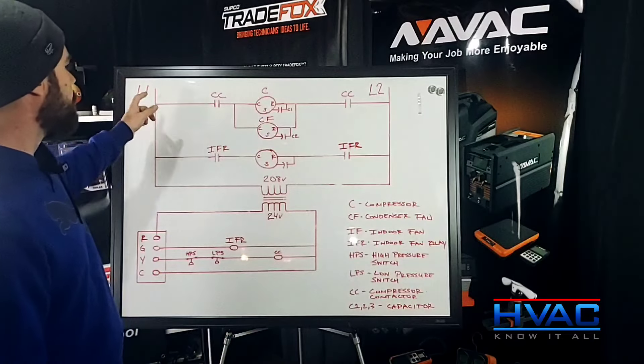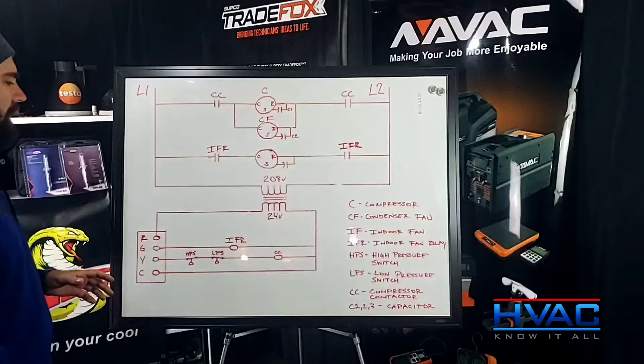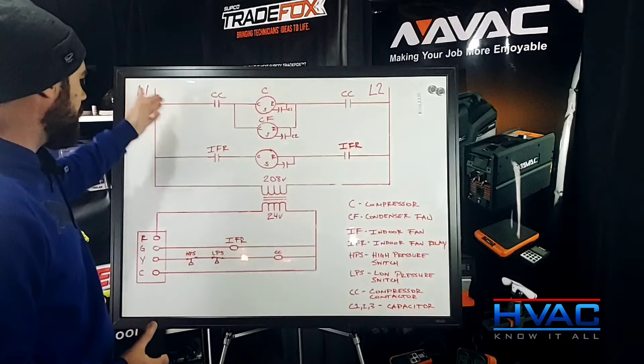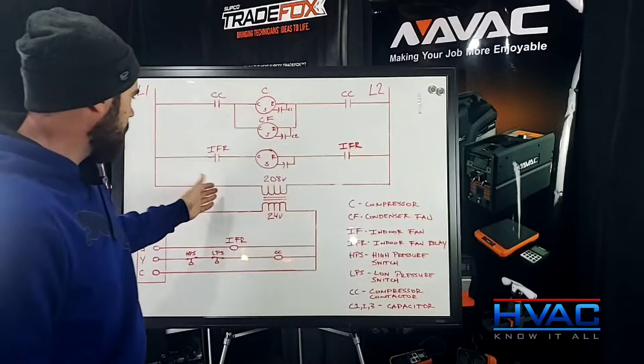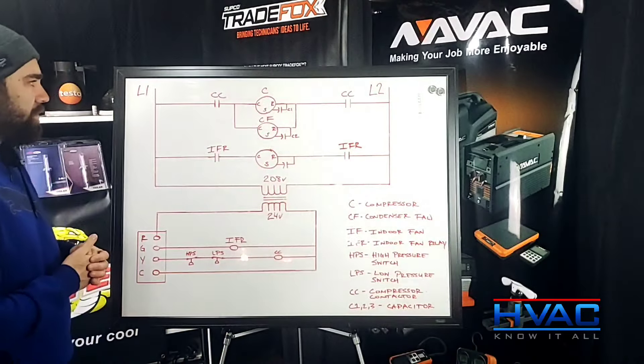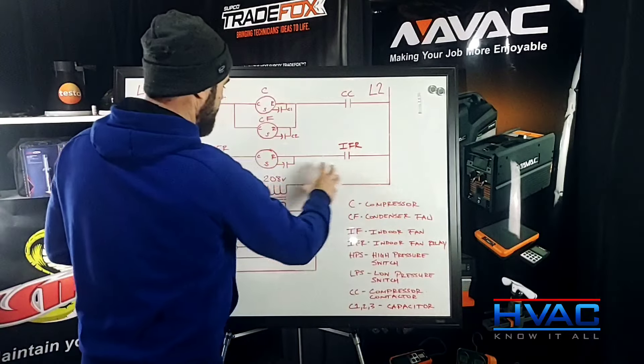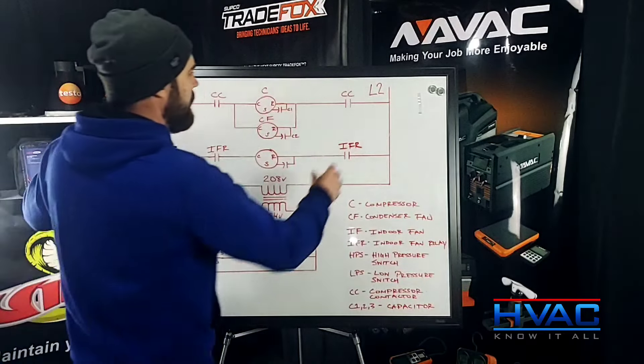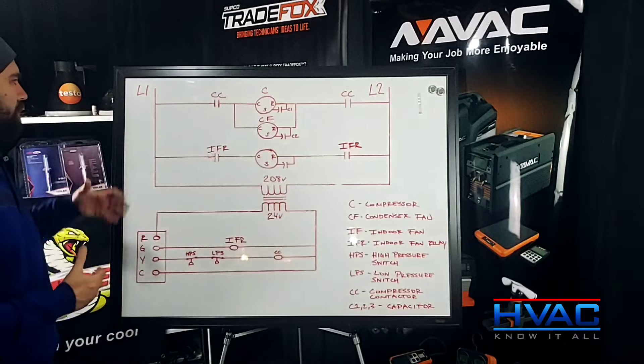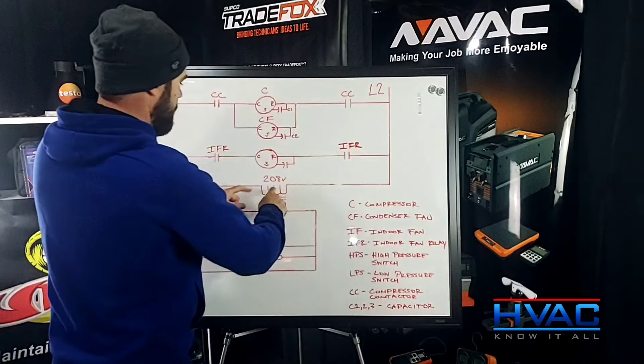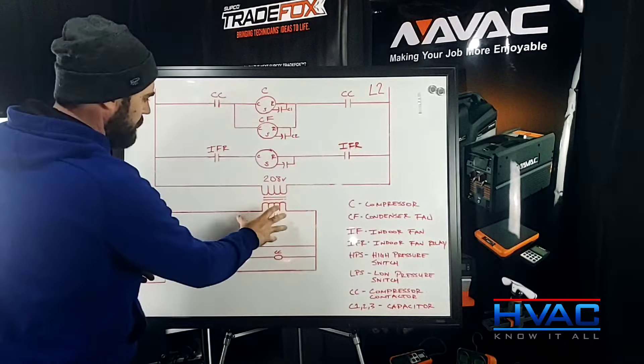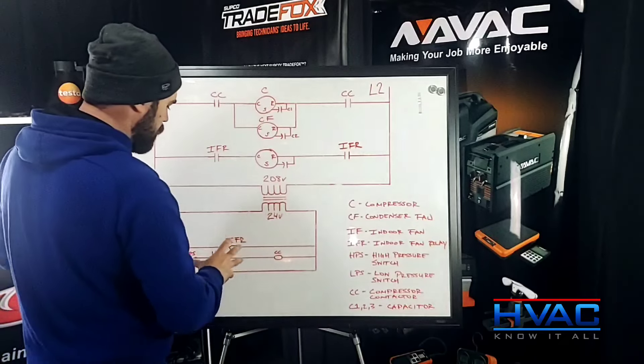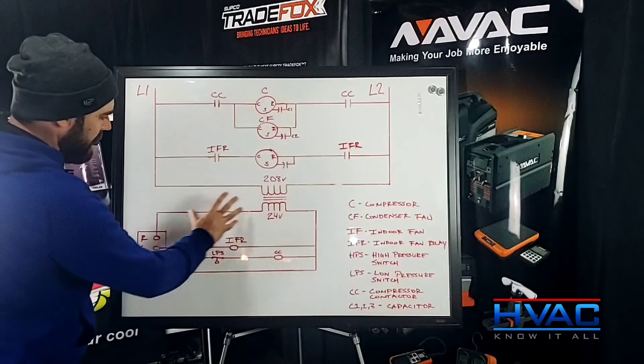I have written line one and line two up here on the diagram. Basically, we have power coming in on both sides. Now on a 120-volt circuit, you will see line one and you'll see common. But on this diagram, it's not — we have power coming in on both sides. This is a 208/230-volt circuit. So if we were to take our meter leads and check here and here, we would probably have anywhere between 105 to about 120 on each side. Now on the low voltage side, we have 24 volts. This transformer is called a step-down transformer — we take a higher voltage and step it down to a lower voltage so we can control everything going on in this diagram from this circuit right here.